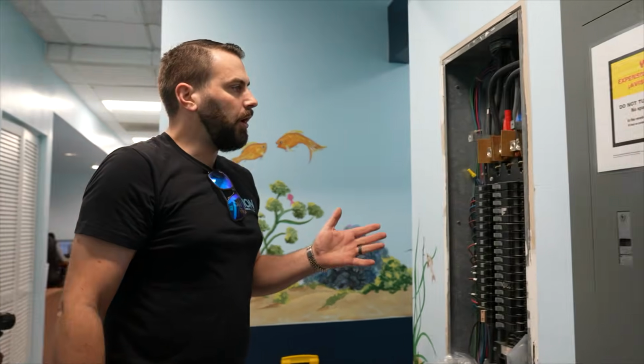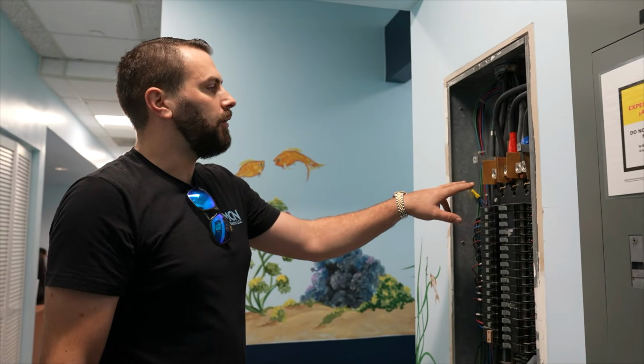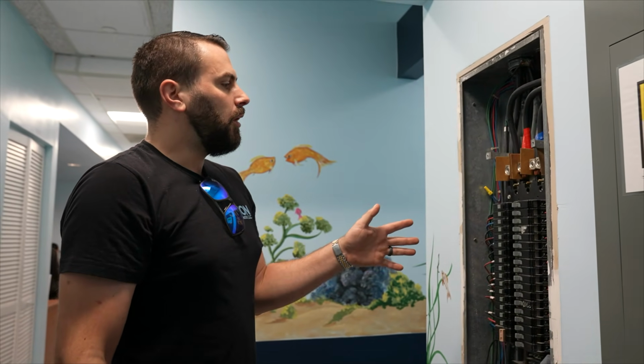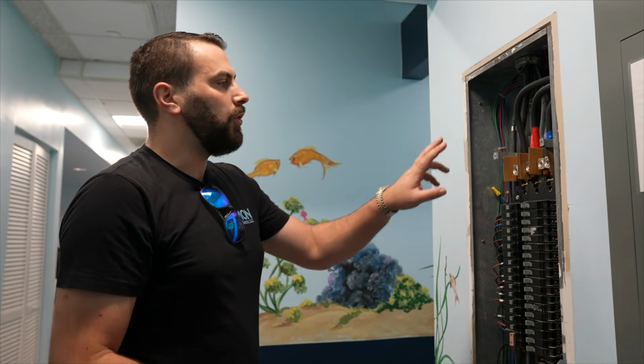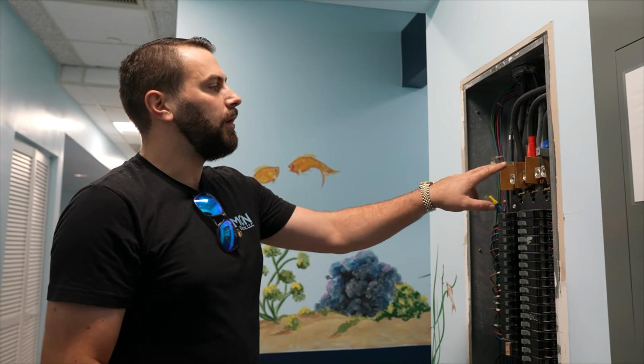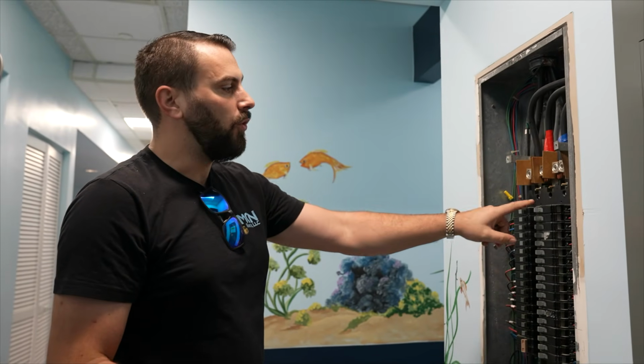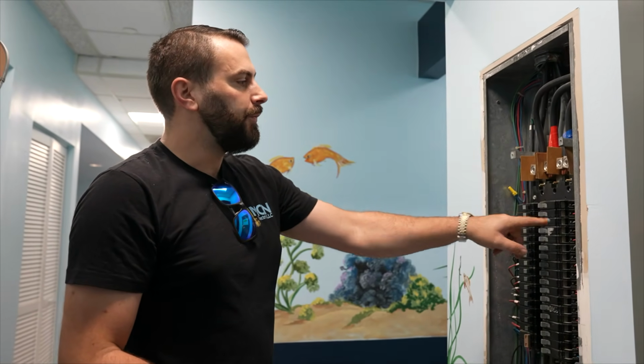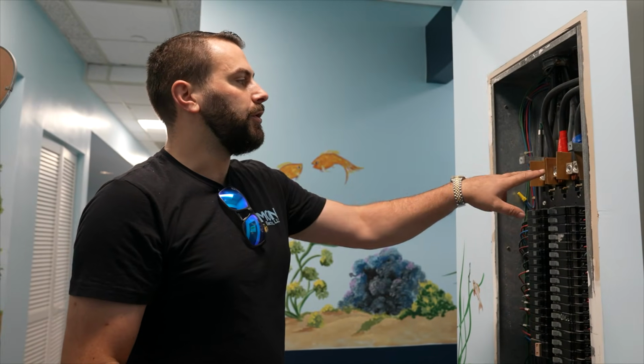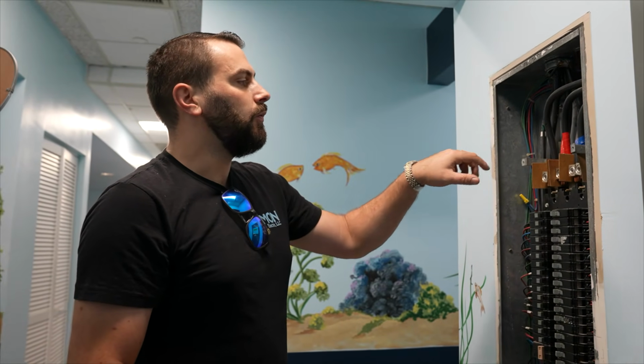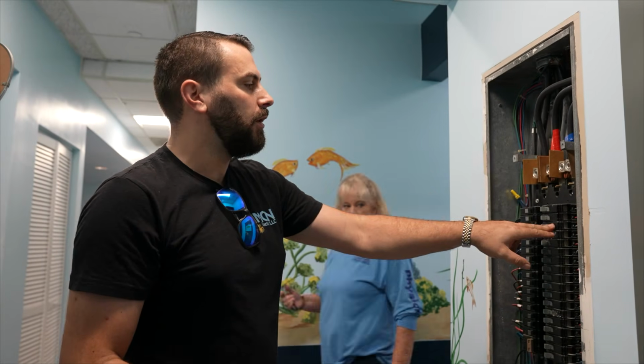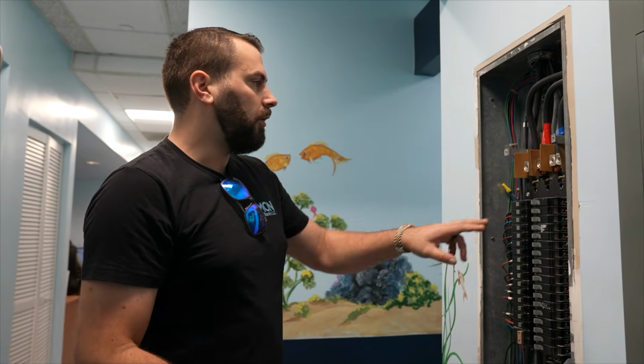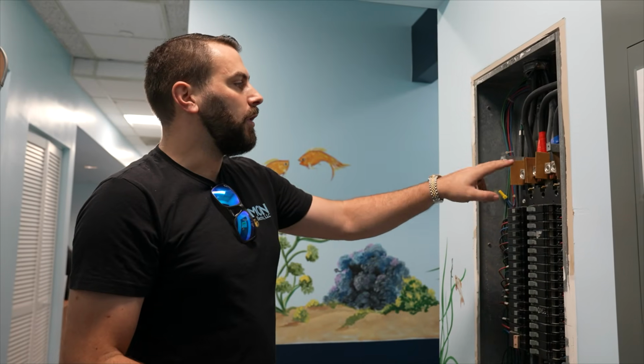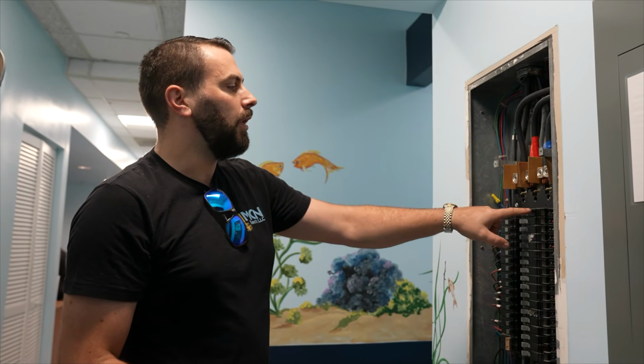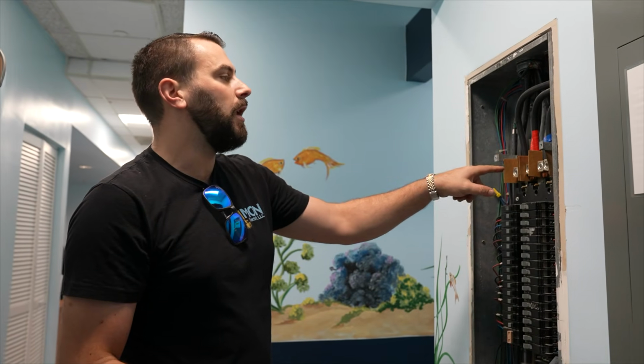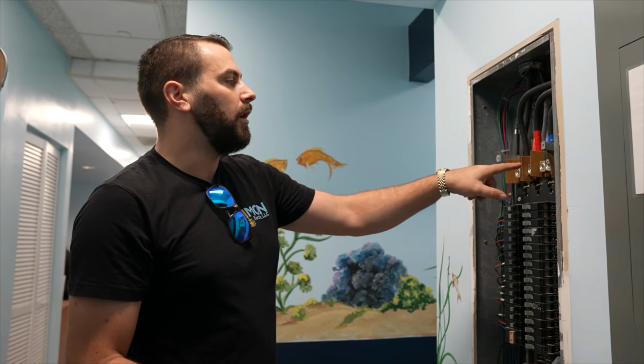So as you saw earlier, you saw me check the voltage on this panel, and that's important because in the 3-phase configuration, there are situations where you have a high leg, either on the B leg or the C leg, and you cannot install a 110 volt breaker in any one of those spots. So for safety, we always check those voltages. And when it's a delta-delta, we can use any one of the A, B, or C leg. And in this configuration we can. But if it was a high leg or a wild leg, we would have to dodge either the B or the C leg depending on where they put the high voltage leg.